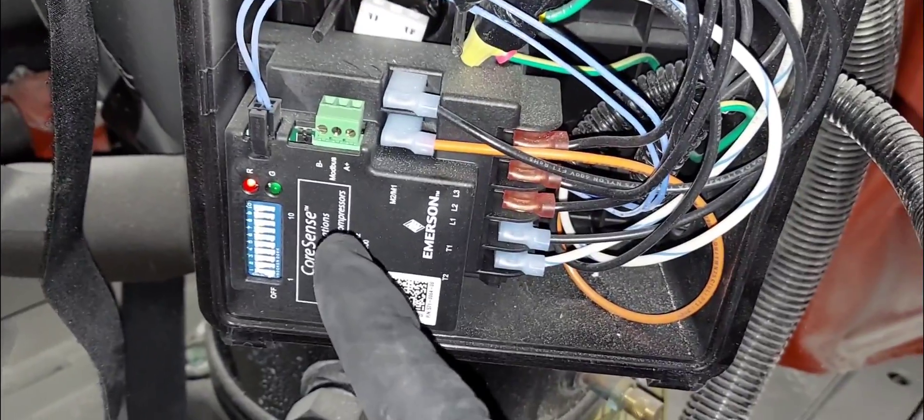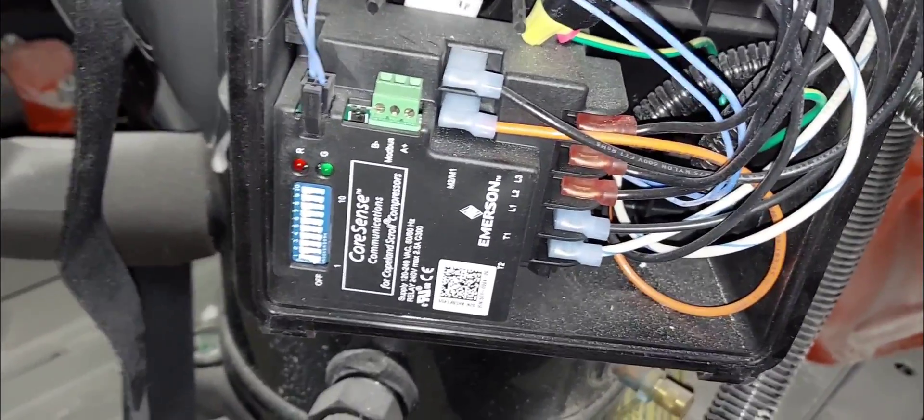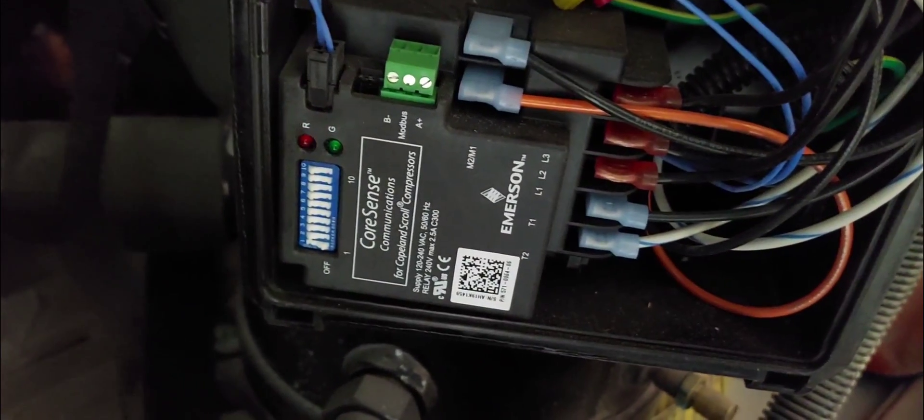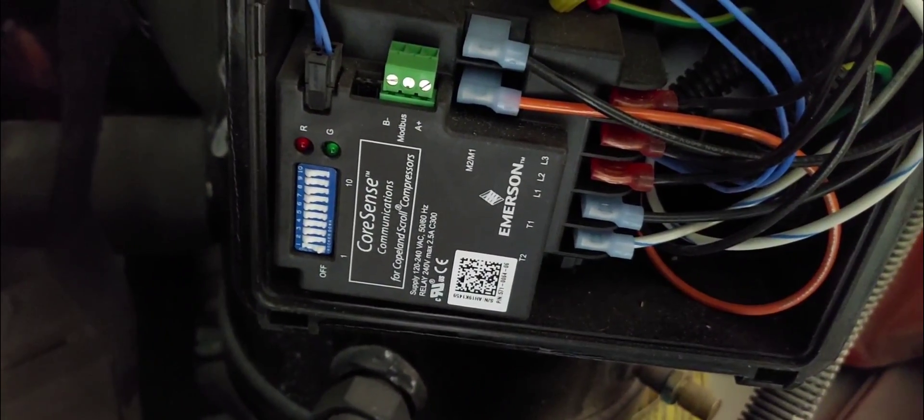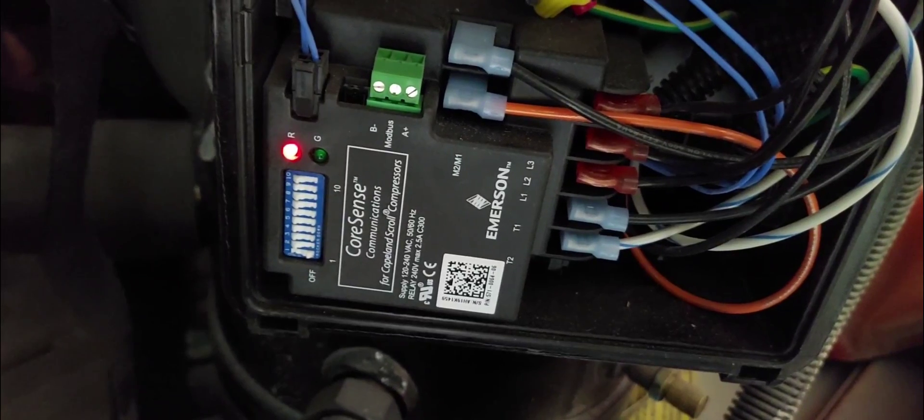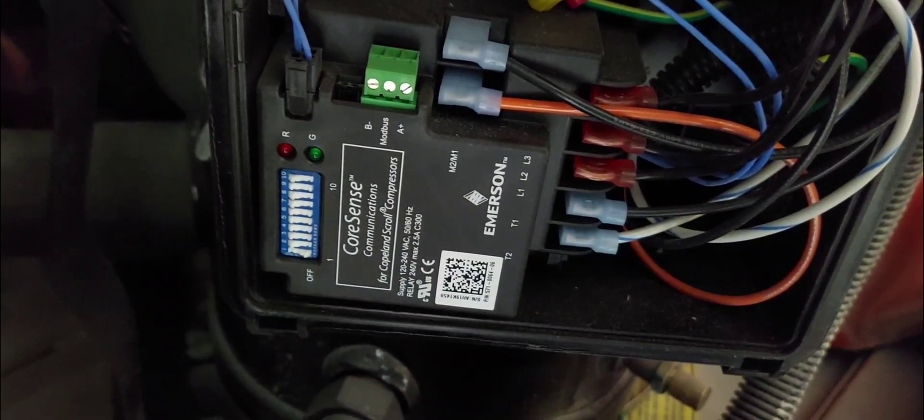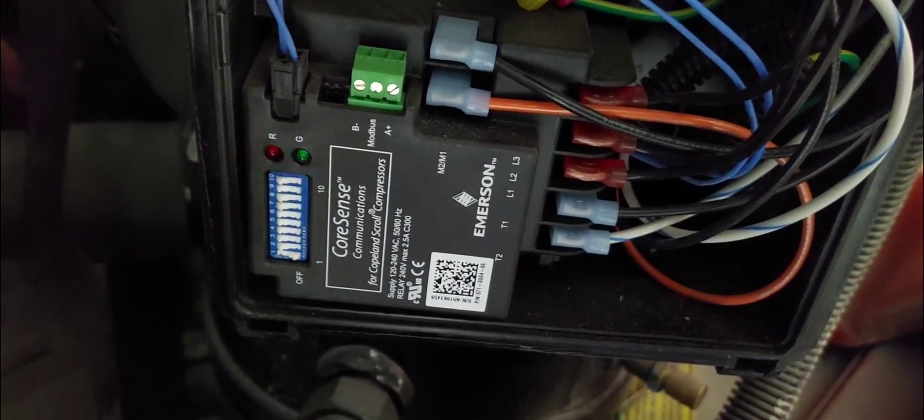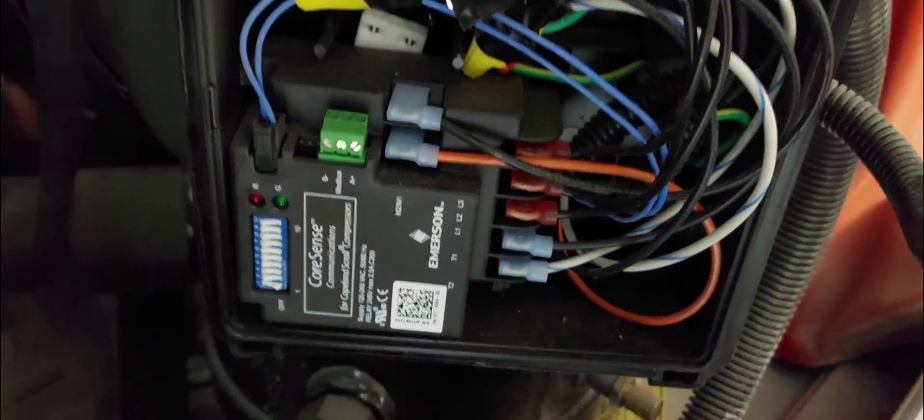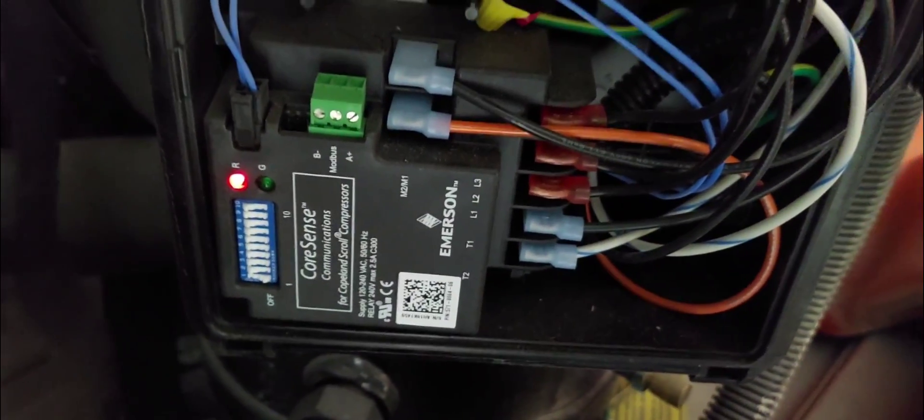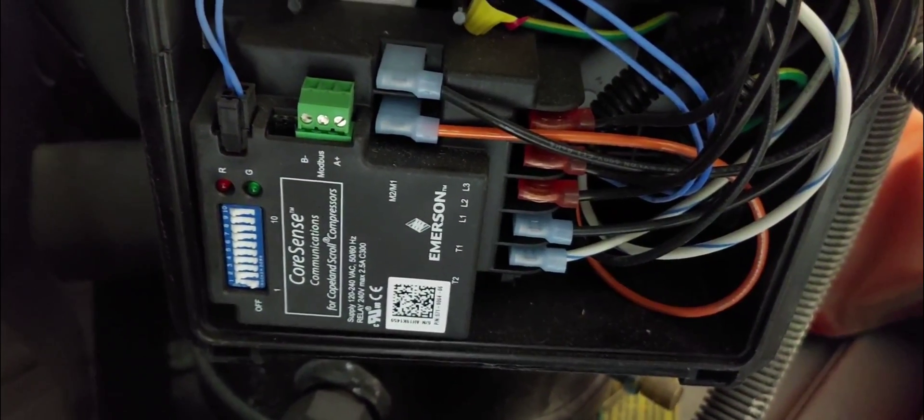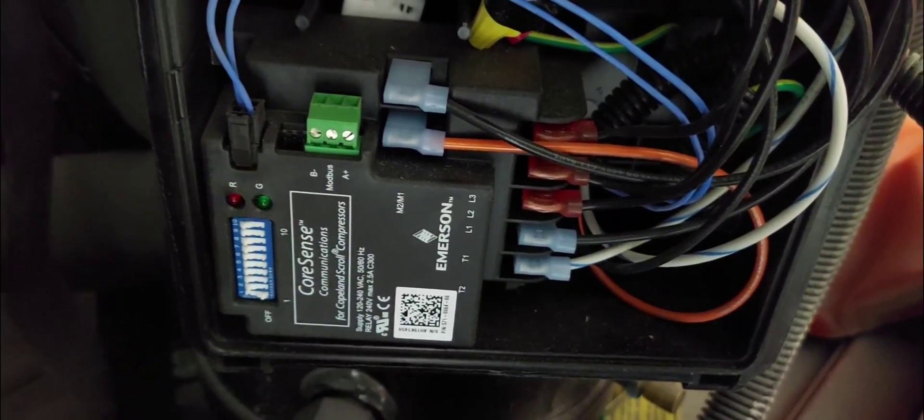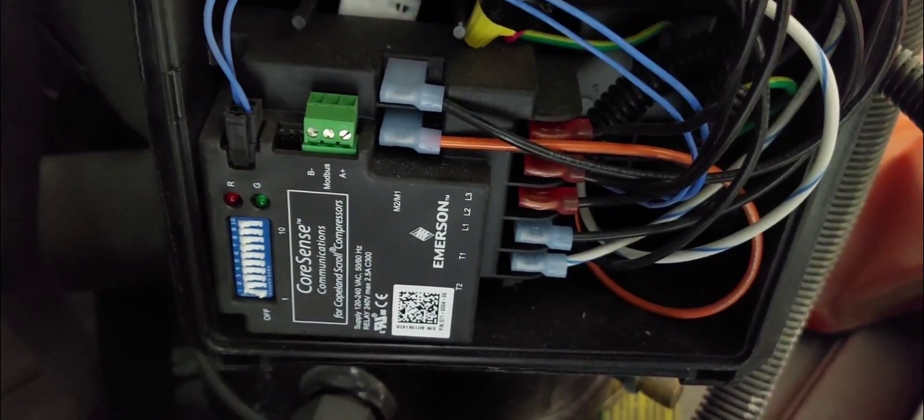Right now you see what's going on in this module. Let me take the light off. The motor protector is flashing a code. Seven flashes. The motor protector is in fault and it's doing seven flashes. Count it again - seven flashes.